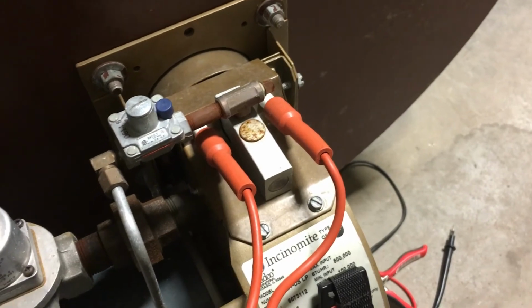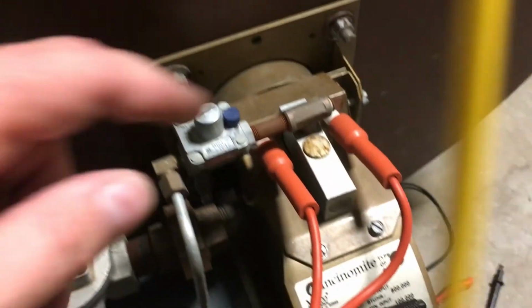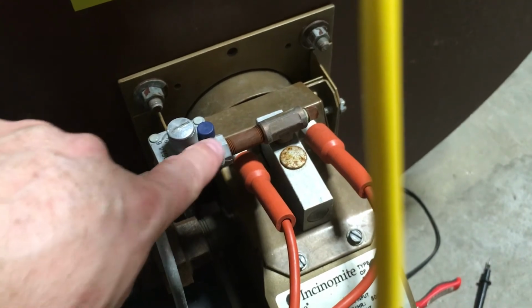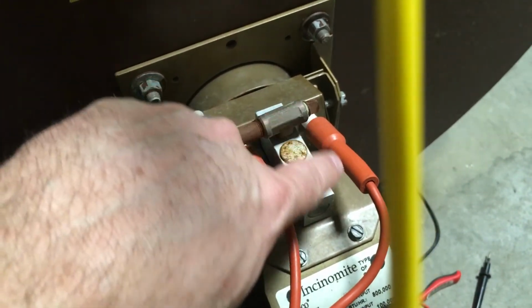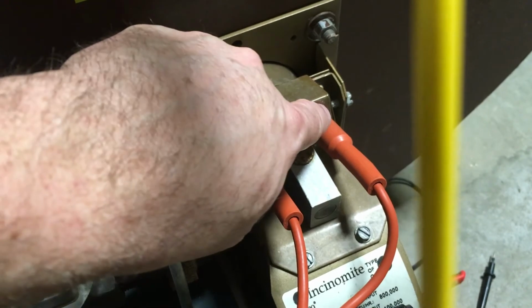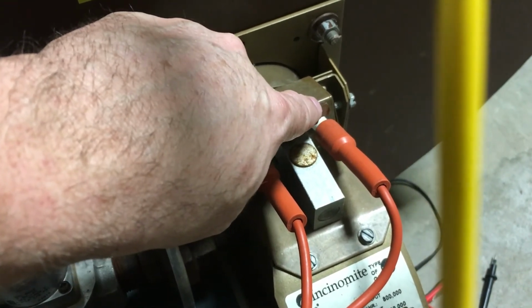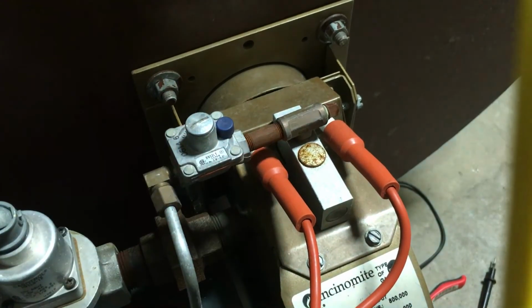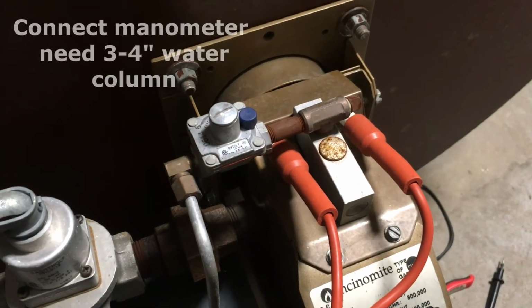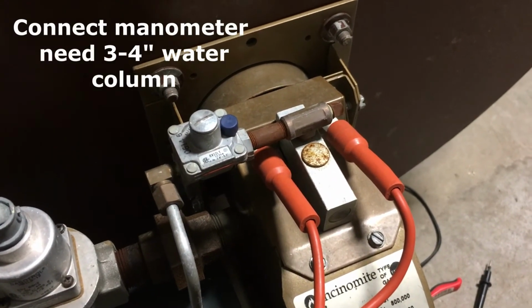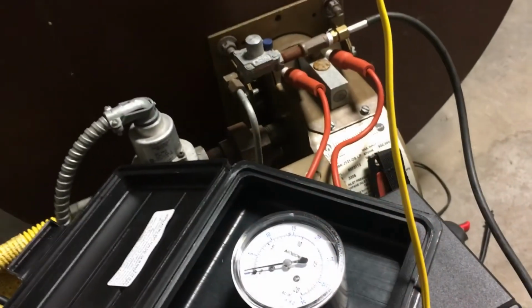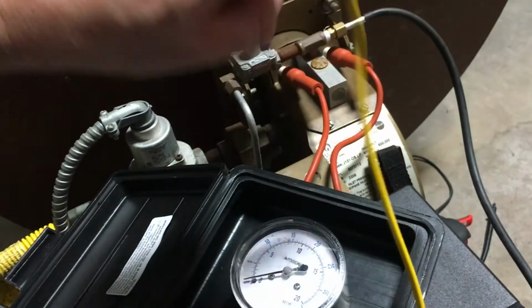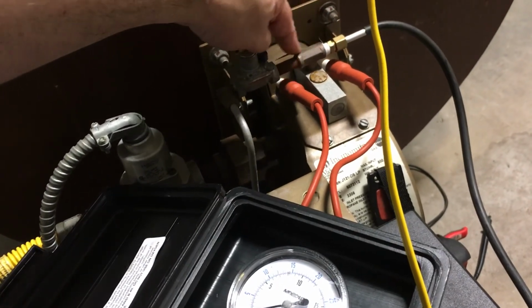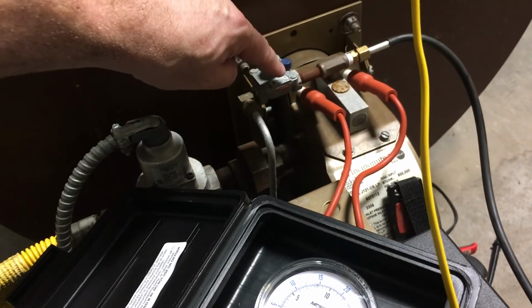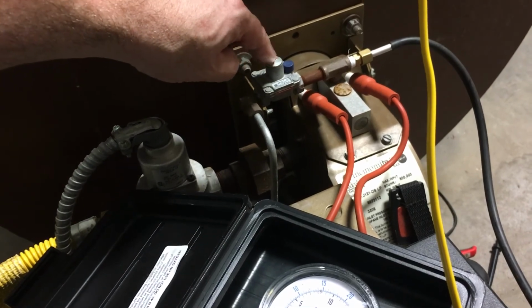We're going to show how to verify the igniter gas pressure, and here's your ignition gas regulator right here, and then there's a T block right here, a T, and a fitting on the end. So I will connect a manometer to this port to verify that we have between 3 and 4 inches of water column. Ideally it should be set at 3.5. Now you can see I have my manometer connected to the ignition gas pressure test port right here. Again, this is your ignition gas regulator. Again, should be about 3.5 inches of water column.